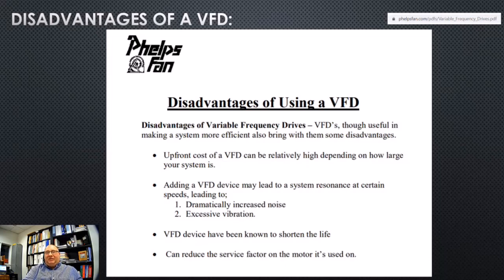A customer may not want to invest in a VFD drive because it costs too much money on the initial purchase. It may lead to resonance at certain speeds, okay, which is known as noise or harmonic distortion, and it could also lead to excessive vibration. Typically, the resonance happens on motors that were really not designed initially to be on VFD drives. There are motors that are sloppy and their service factors are not that clean. So by putting a VFD on an older non-VFD rated motor, this is bound to happen, and it is some of the side effects. So we call it noise or vibration, also known as harmonic or resonance.